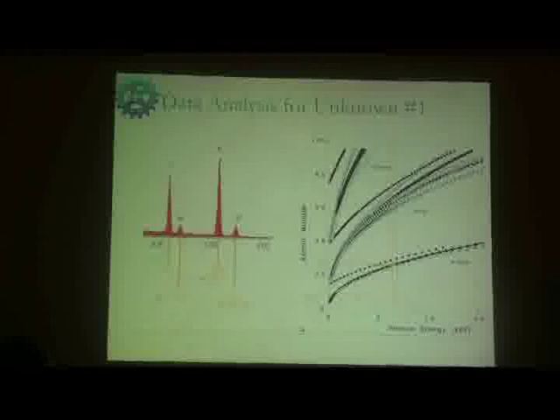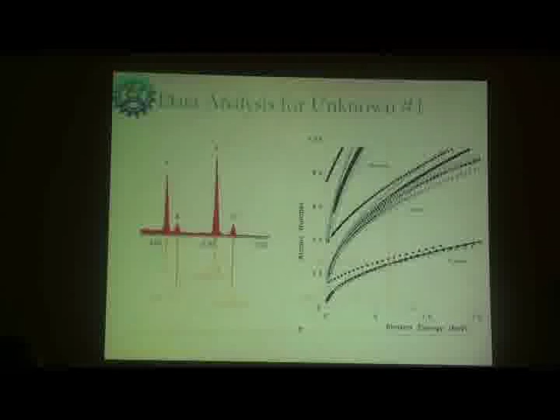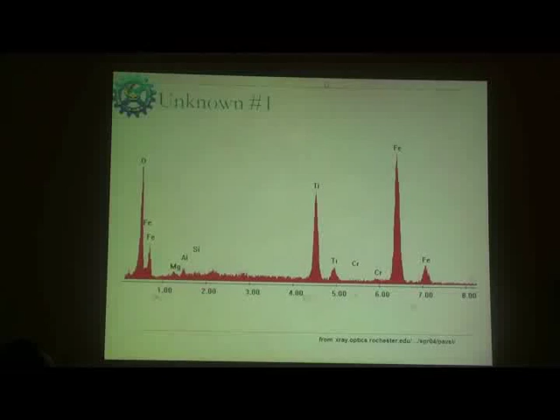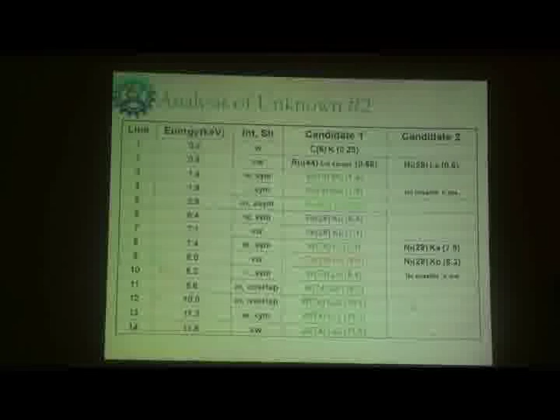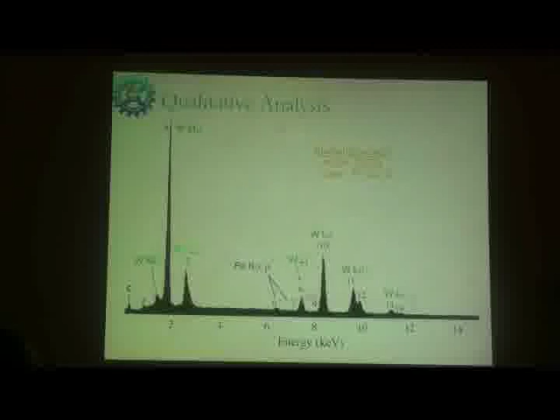So you can detect the element by taking the energy and cross-referencing it to the atomic number, and you can detect that particular element without any computerized method. The same thing can be fed into the computer, and you can say that these are the energy levels for this particular element, and you can detect those elements automatically. So all the elements can be detected like that, from 1 to 10: iron, titanium, copper, silicon, all these things. The unknown 2 also can be done. So this is how you can do these things. These are the qualitative analysis.